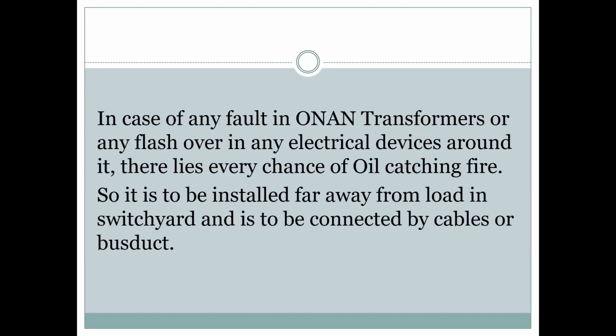Next. In case of a fault in the transformer, any flashover in electrical devices around it, there is every chance the oil will catch fire. So it is to be installed far away from the load, in the switchyard, so it is connected by cables. So it is an additional cost. The cable I am buying and the bus bar are an additional cost for me. If I could put the transformer in front of the load, then my bus bar and cable cost would have been solved. So my project cost would have come down. So that's why the dry type transformer is coming as the next generation transformer.